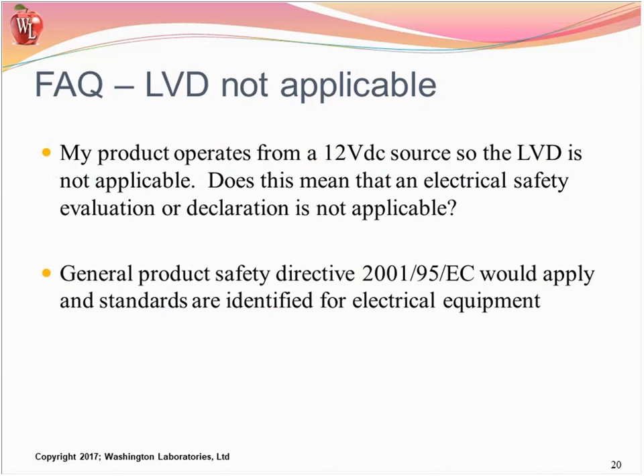My product operates from 12 volts, so LVD is not applicable. Does this mean that an electrical safety evaluation or declaration is not applicable? The Low Voltage Directive would not be applicable; however, the General Product Safety Directive 2001/95/EC would apply, and standards are identified for electrical equipment.